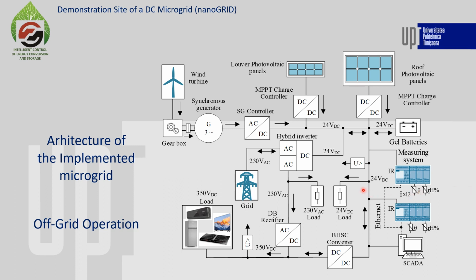There are also loads on the low voltage DC bus, such as the lighting system, which was implemented using LED strips directly connected to the bus, the sensors measuring temperature, humidity, and CO2, also directly connected to the bus, and the automation and the SCADA system. The communication between all devices is ensured using the Ethernet network protocol Modbus TCP/IP. The total number of devices that communicate and exchange information is 21, including the BHSC converter, maximum power point charge controller, the synchronous generator controller, and so on.